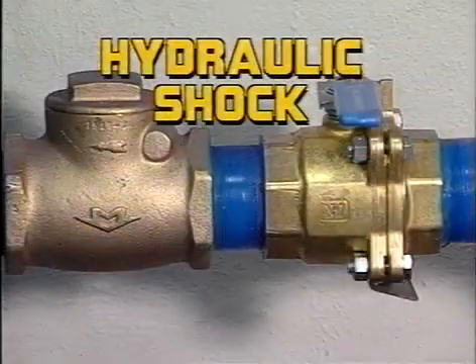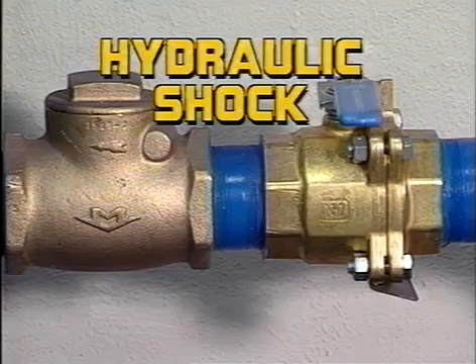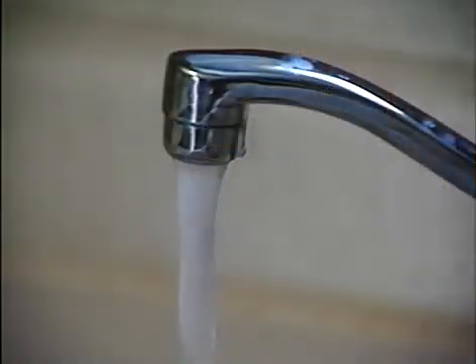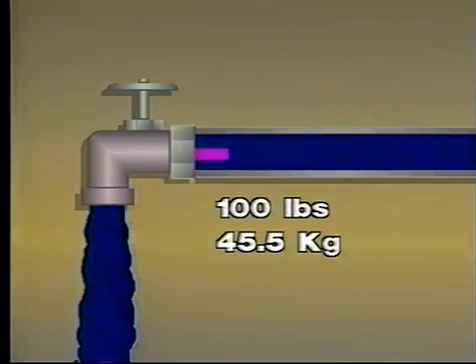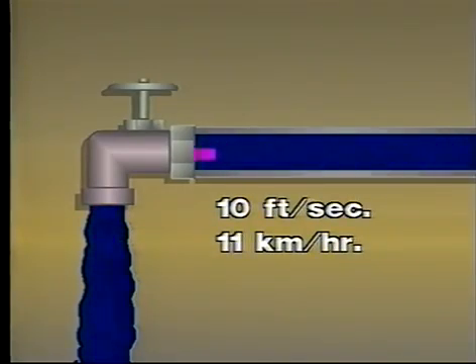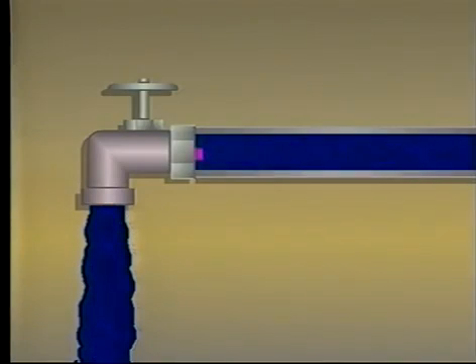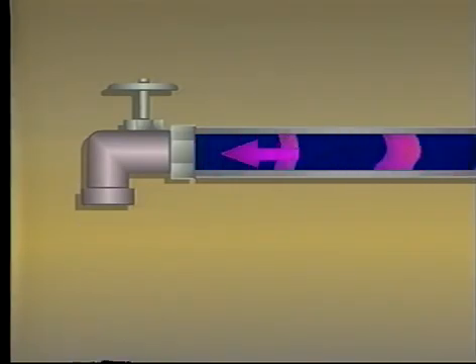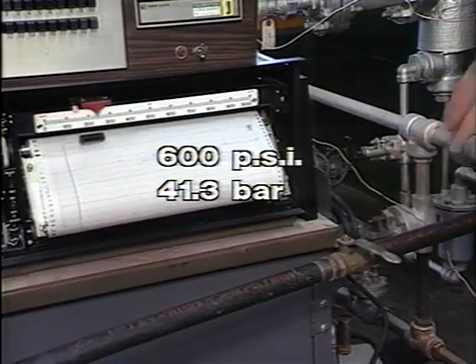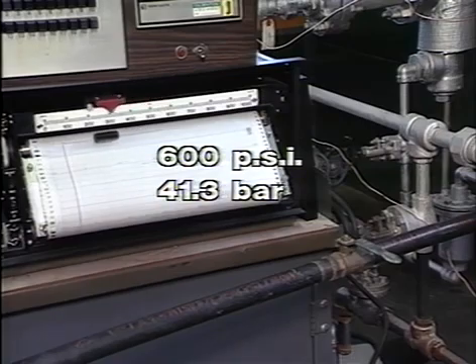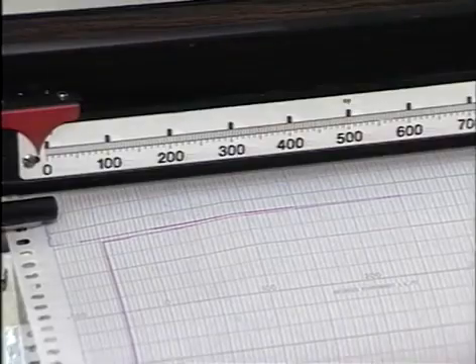Hydraulic shock occurs when a valve is closed too abruptly. When a water valve is open, a solid column of water moves from its source at the main to the valve outlet. This could be 100 pounds of water flowing at 10 feet per second, or about 7 miles per hour. Closing the valve suddenly is like trying to instantly stop a 100 pound hammer. A shock wave of about 600 psi slams into the valve and rebounds in all directions, expanding the piping and reflecting back and forth along the length of the system until its momentum is dissipated.